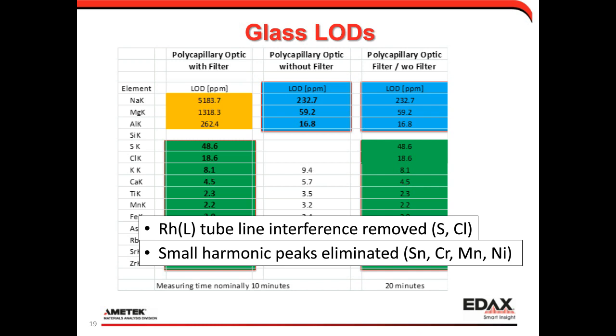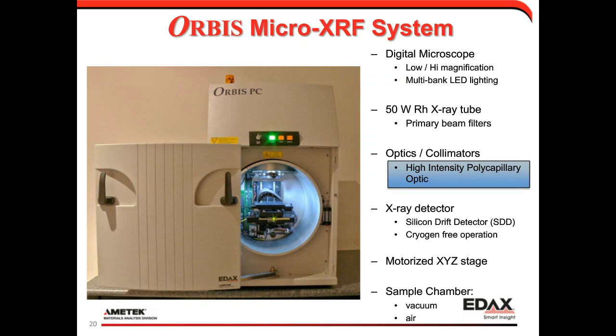So the benefit of combining results with and without a filter is that you can clean up various artifacts to get a clean shot at trace and minor peaks. Coming back to the equipment: under the optics section, we're using high-intensity polycapillary optics, which collect as much X-ray coming through the filter as possible to get the best results. Measurements are with spot sizes on the order of 25–30 microns full width at half maximum.